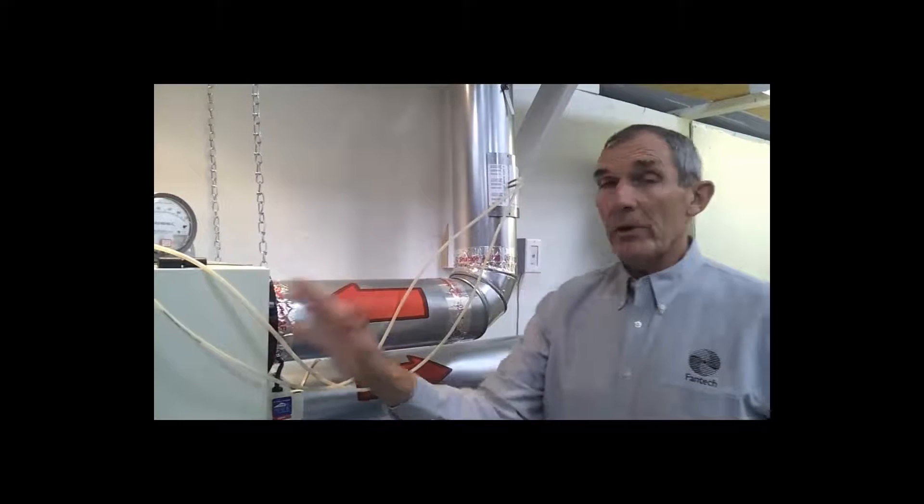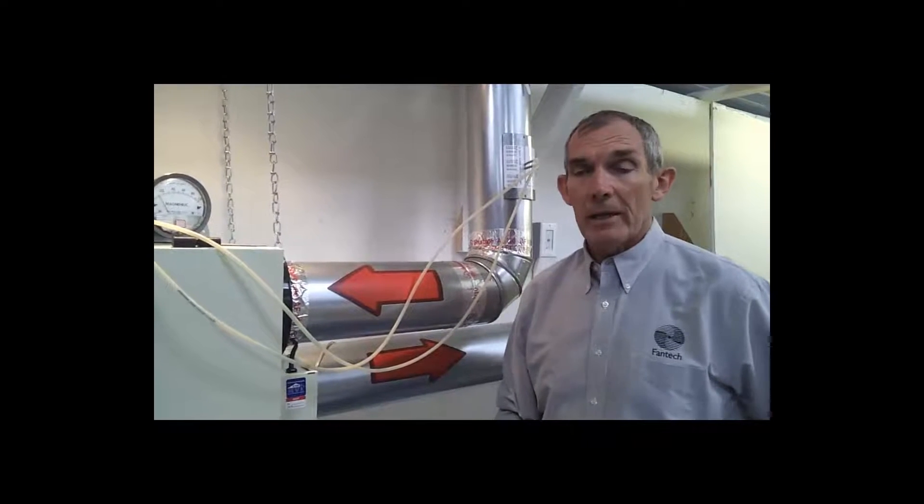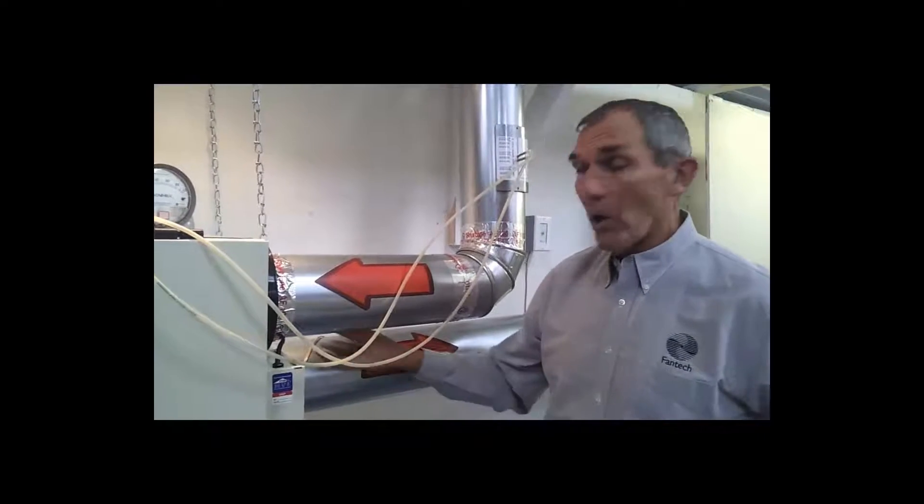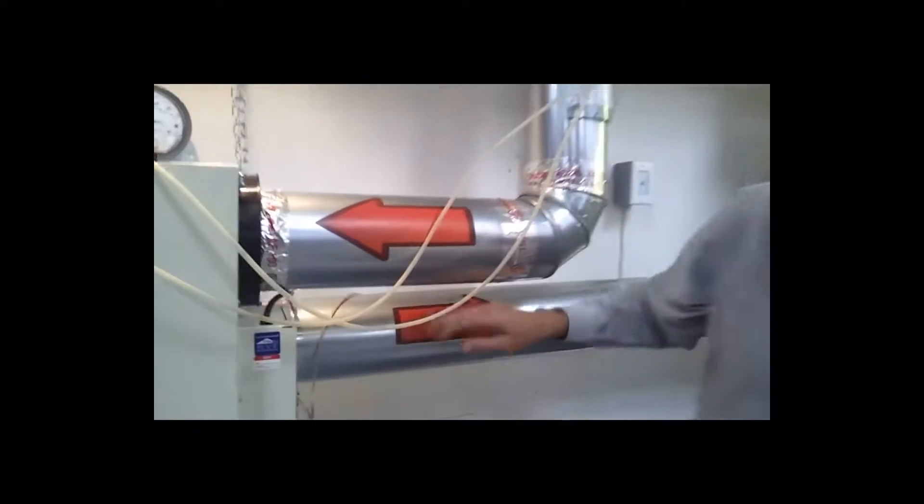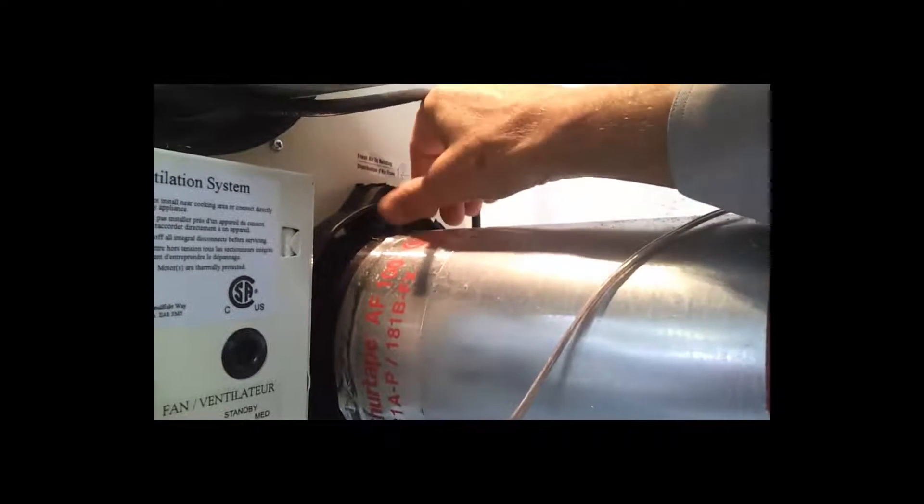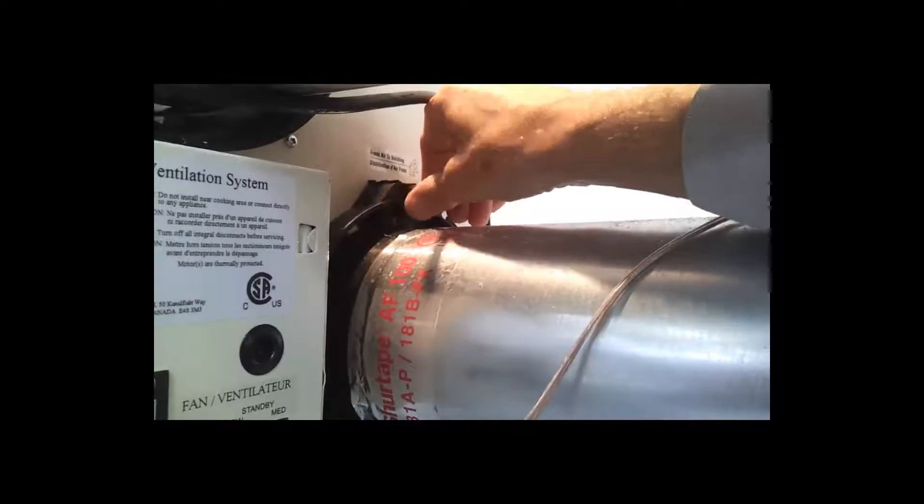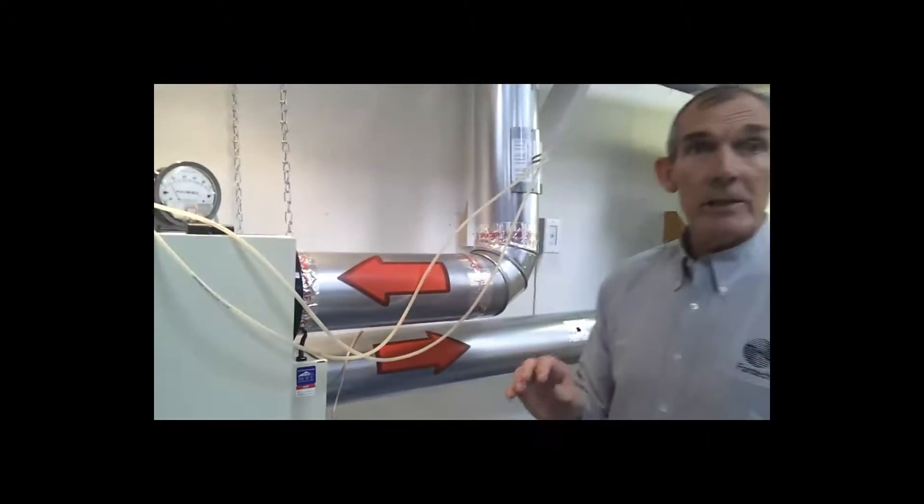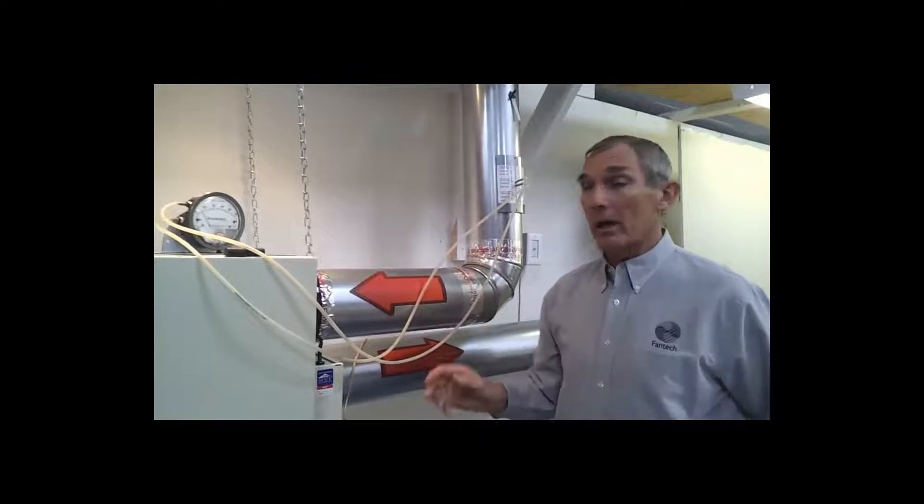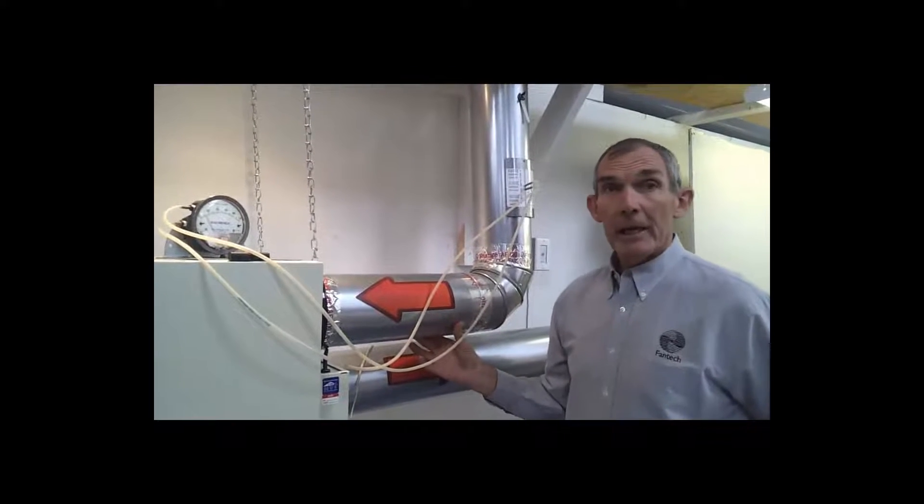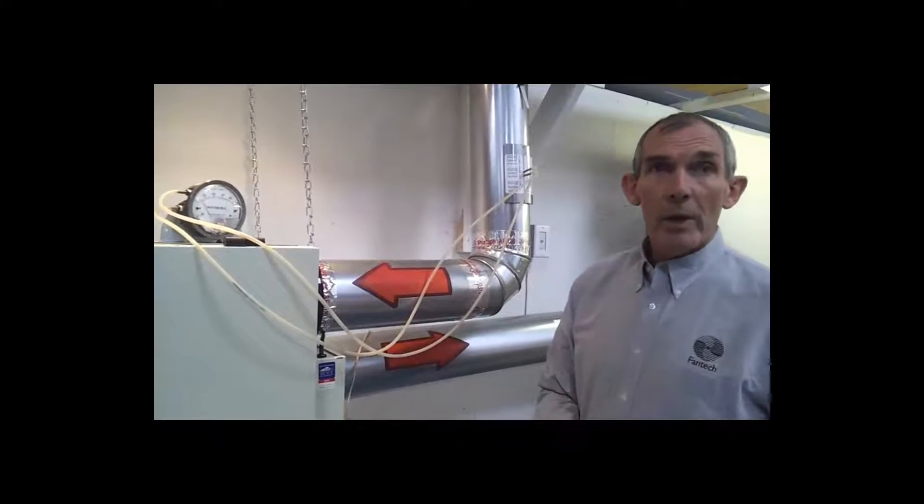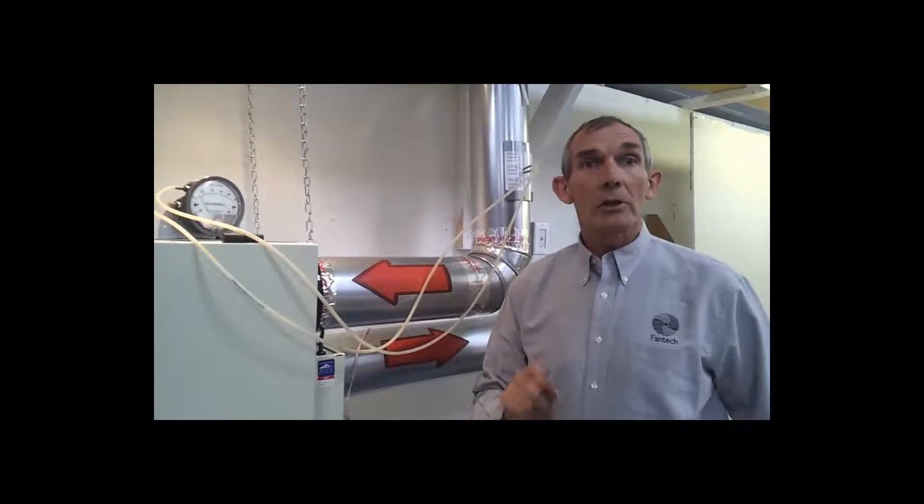With all Fantech HRVs or ERVs, it has its own integral balancing damper on the supply side. Down here we have a screw-type balancing damper that opens or closes. Only in this case, we see that the high side or pressure is on the return side. In this case, what we have to do is insert a balancing damper.